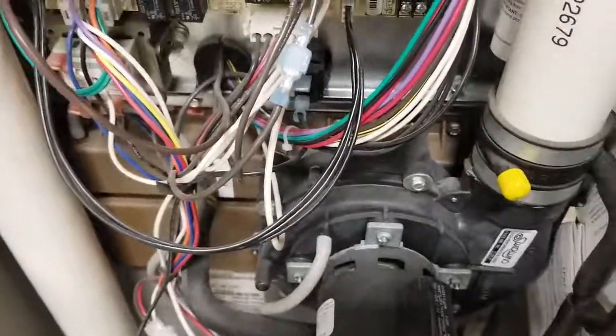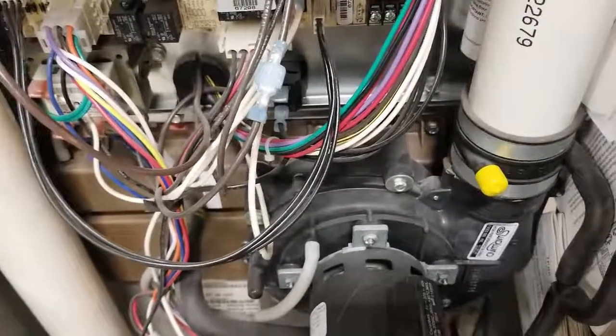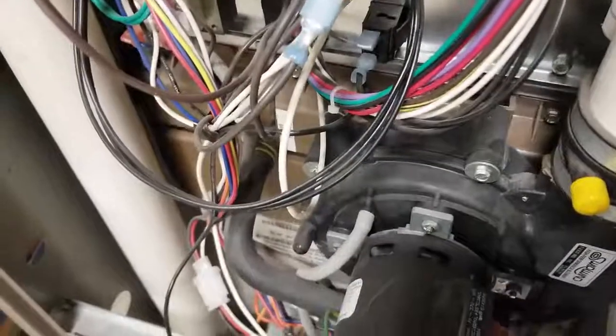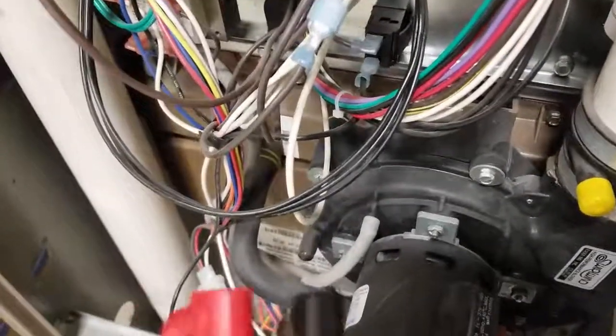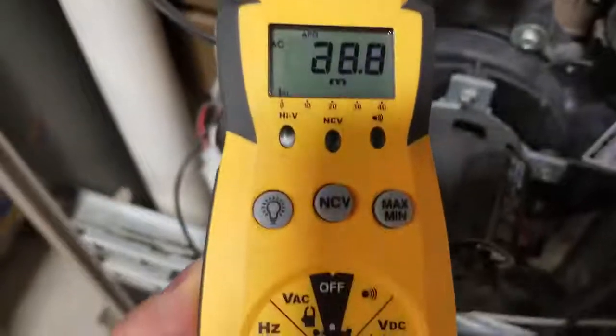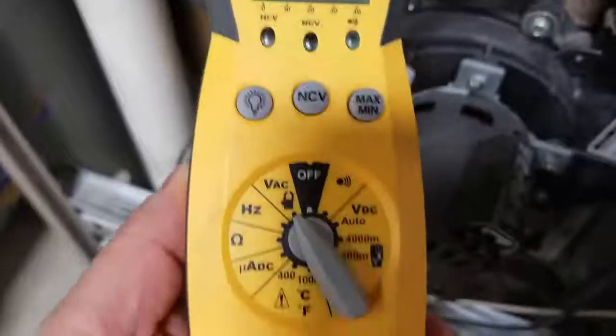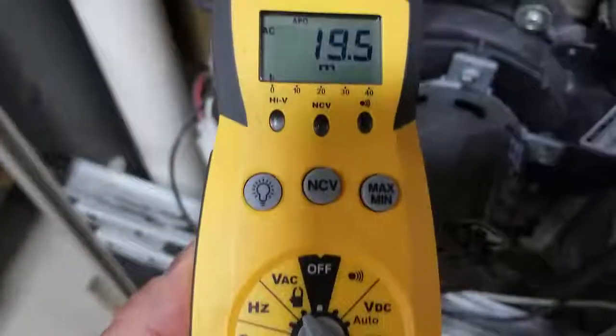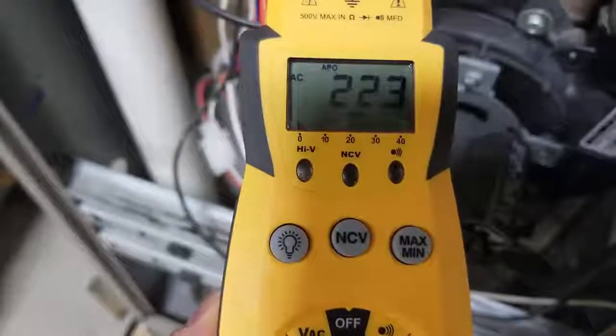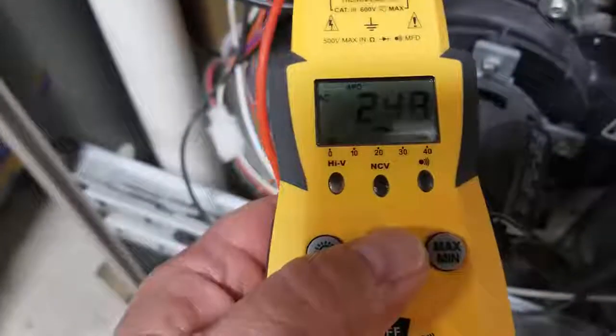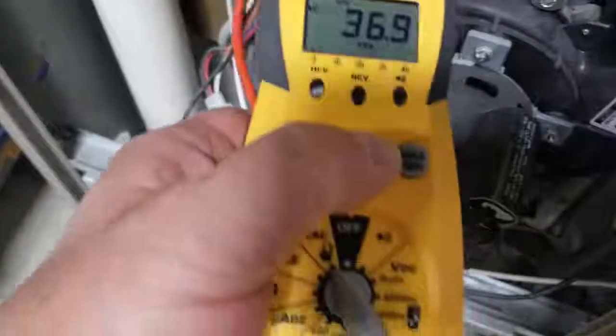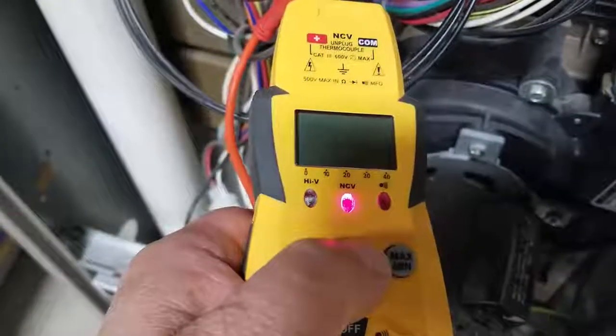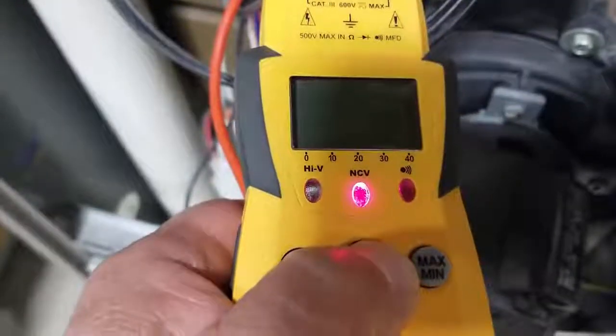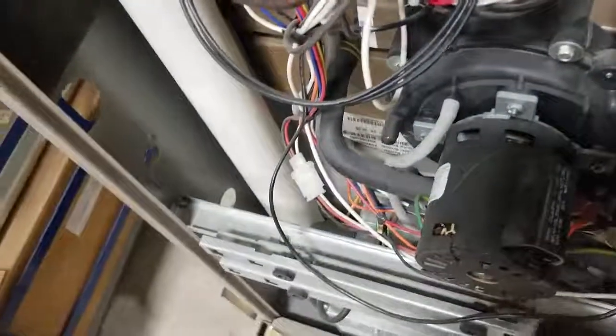Okay, I'm going to show you guys why using a non-contact voltmeter to troubleshoot furnace problems is really a horrible idea. So here we have a meter. It's a multimeter, volt-ohm meter, and it will detect non-contact voltage. So basically all I have to do is push this button, and if there's voltage present, it'll let me know. Voltage present. Now we can go ahead and check that voltage and verify what it is.